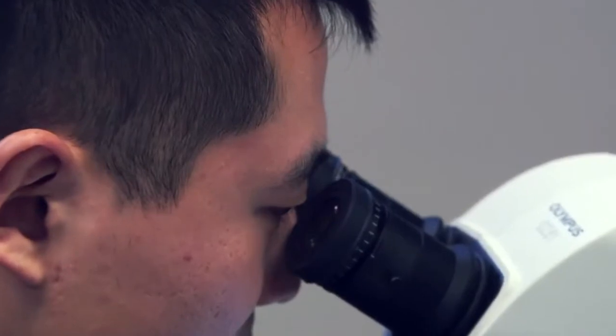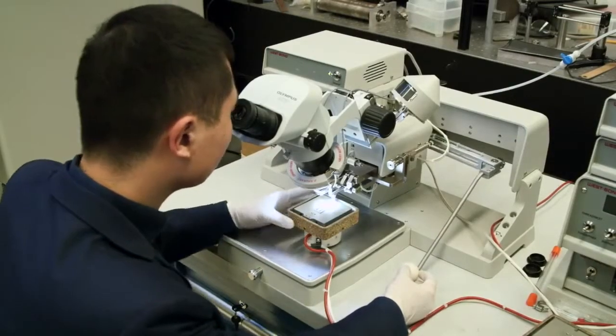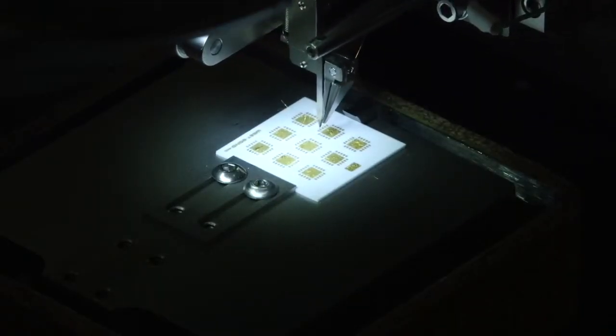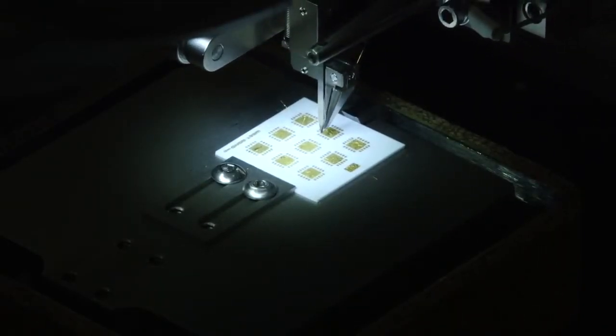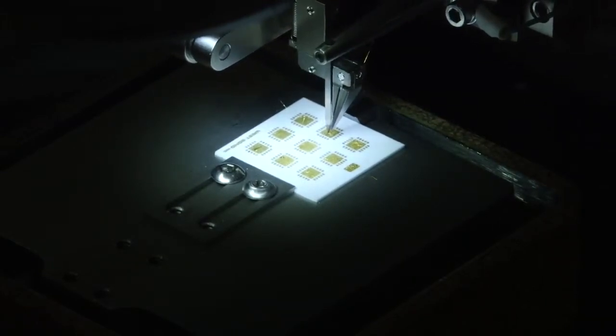Next, turn on the bonder and use the joystick to maneuver the tool towards the center of the bond pad. Lower the tool and you will hear a clicking sound. The head of the bond is now formed. After the first end of the wire is attached, create a loop and form a second bond on the substrate. Repeat the process for the next wires.